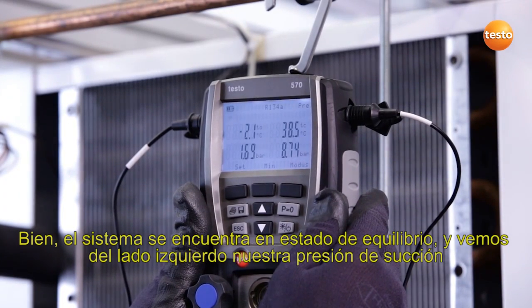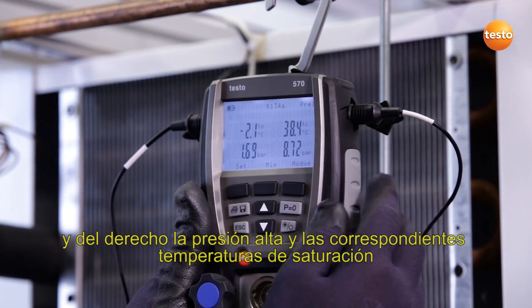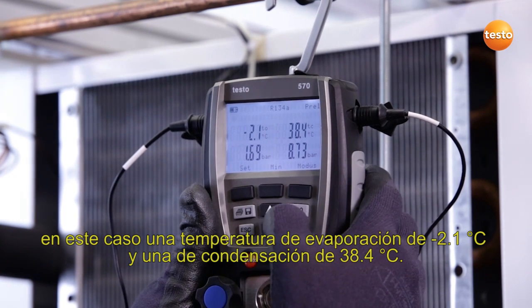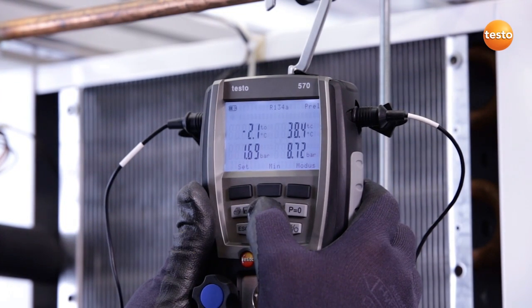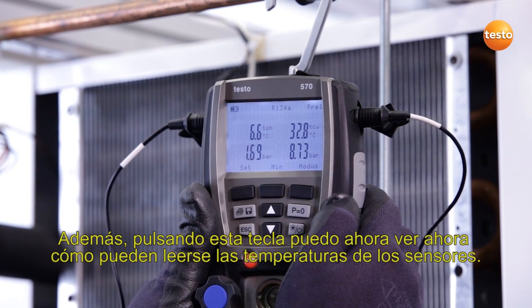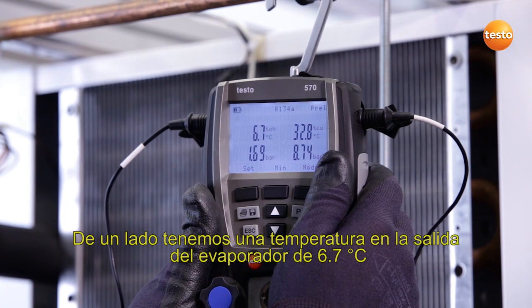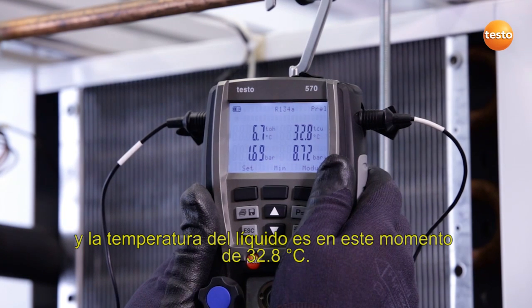The system is now in a steady state and on the left-hand side we can see our suction pressure. On the right-hand side, the high pressure and the corresponding saturation temperatures — in this case, -2.1 degrees Celsius evaporation temperature and 38.4 degrees Celsius condensation temperature. This suits the ambient conditions very well right now. By pressing this button, I can also see the probe temperatures: 6.7 degrees Celsius at the exit from the evaporator and a liquid temperature of 32.8 degrees Celsius.